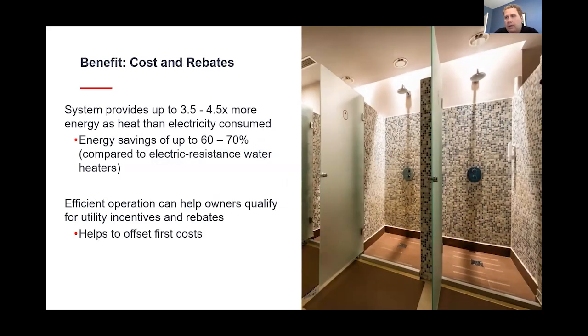Additionally, because of the COP, which is the coefficient of performance, which is basically how much energy you put into a system versus how much energy you're going to get out of it, we have 3.5 to 4.5 times more energy as heat than electricity consumed. This will allow owners energy savings of up to 60-70% compared to electric resistance water heaters. So it's definitely a much better option compared to those types of systems. And in some markets, there are even going to be incentives to move towards these types of products. And we've seen them across the country. Different markets are moving that way already.